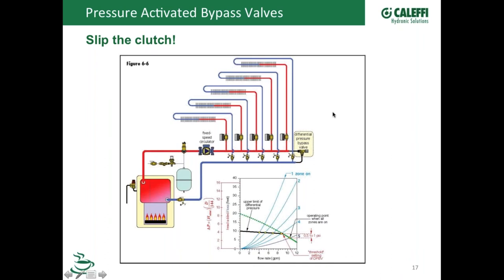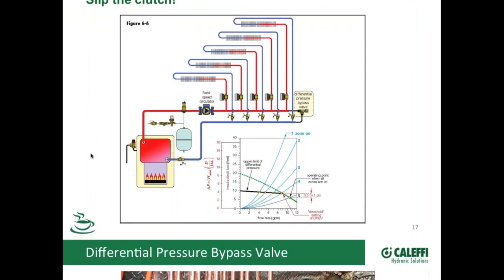And one other thing I wanted to say about this picture is this valve could really be installed back here. And in some cases, that may be desirable, because if this was a long header in the mechanical room, or maybe it went around the loop of the mechanical room or something, as this pump is running and these zone valves shut off, you've got all that heat loss going through all this piping. So if you had the valve back here and just this valve is open, you just have flow through this much of the circuit. You're not flowing through this entire header pipe at supply and return coming back, because your valve is bypassing right down here. So the valve doesn't have to be at the end here necessarily. I mean, if it's a short run of a couple feet like that in the mechanical room, no harm there, but just know that it can be installed right by the pump also.